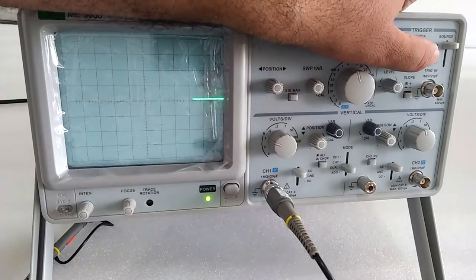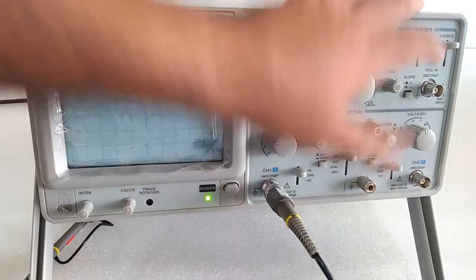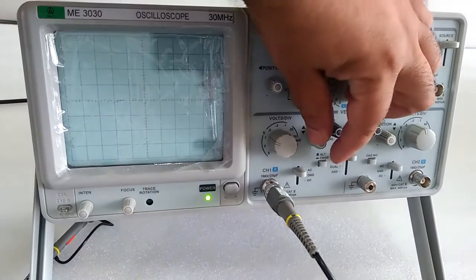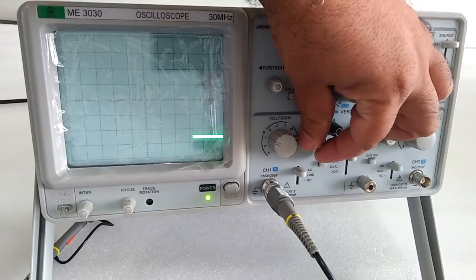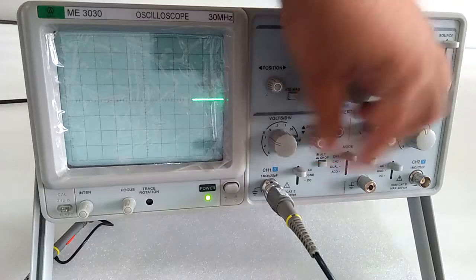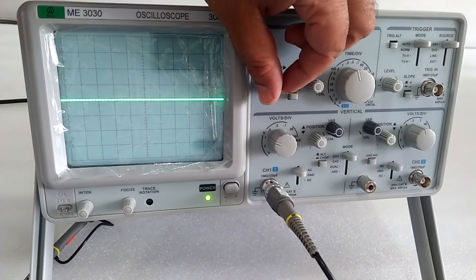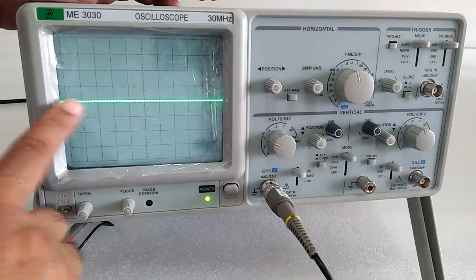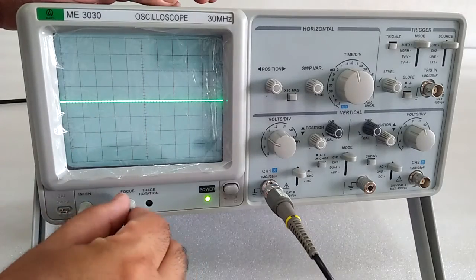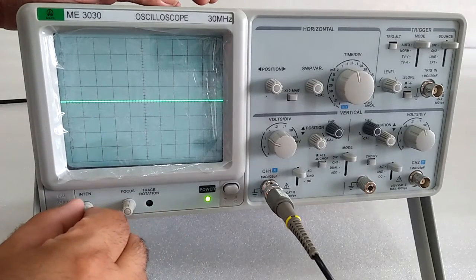Put the mode switch on auto and set it to channel 1. Using channel 1 up and down controls, you will get the baseline. Get the position complete. After getting the line, you have to set the focus and intensity as well.